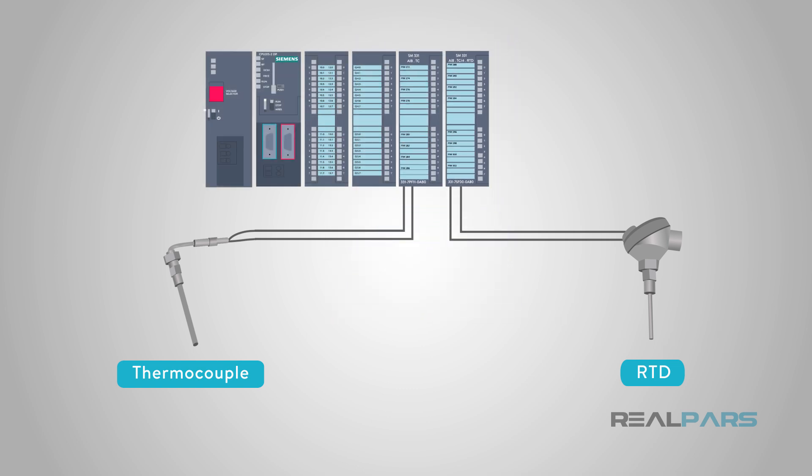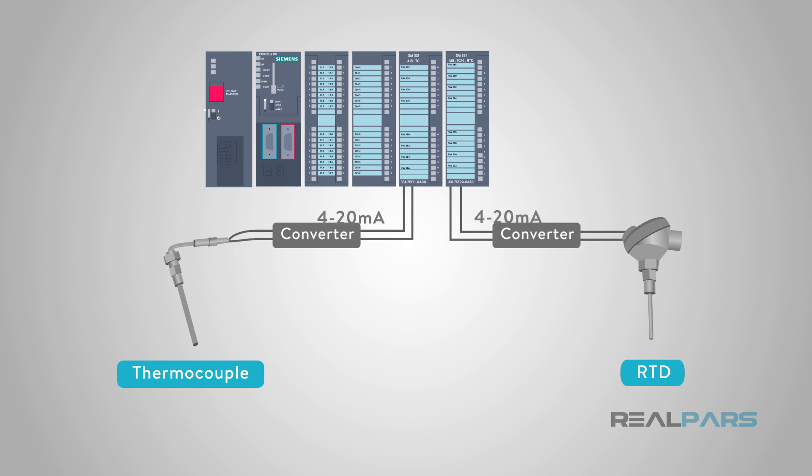The rest of the signal categories are converted locally into a more generally understood form of signal, either voltage or current, before being connected to the control system. If the temperature signals have to travel very far to the control system, we usually convert them like this also. The most commonly used standard today is the 4 to 20 milliamp signal, because of noise immunity and other characteristics. And every type of analog sensor I have mentioned can generally be purchased in that type of output.